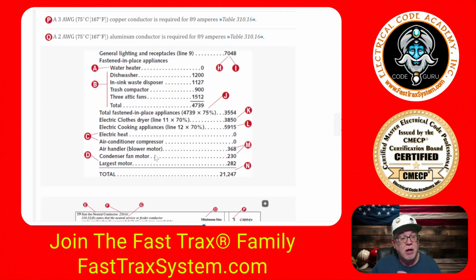Absolutely. Now, the other question I get from people is, well, wait a minute, Paul. When I was sizing the ungrounded hot conductors using the standard method, I had to compare heat versus AC, and whichever was larger, that's what I took. And if heat was larger than the AC, then I got rid of the AC's contribution and just went with the heat. And that meant that I would have lost the condensing fan, for example, right? That doesn't work that way for the neutral. You don't do a heat versus AC comparison.